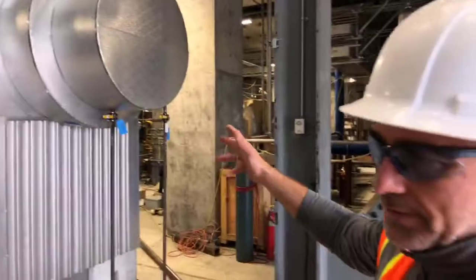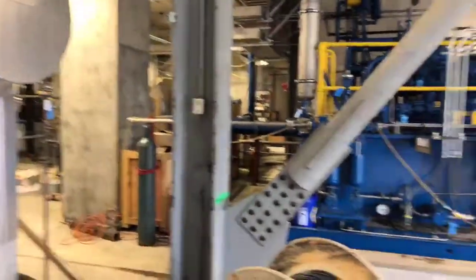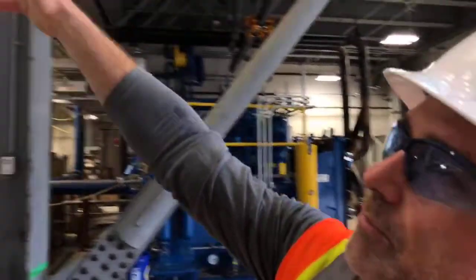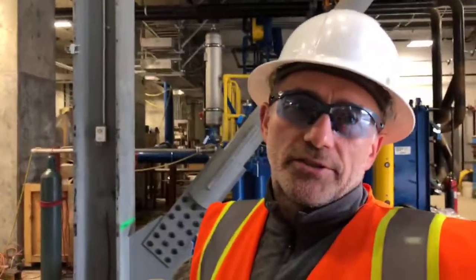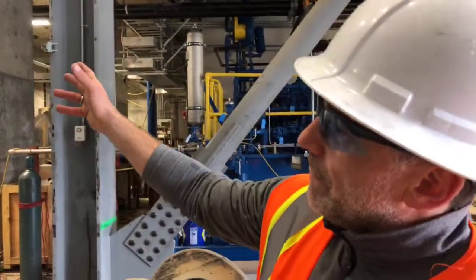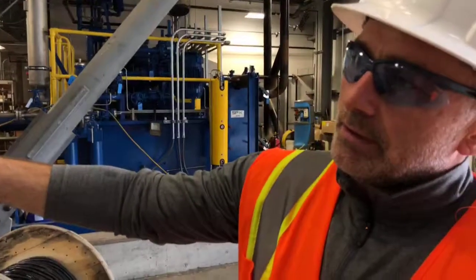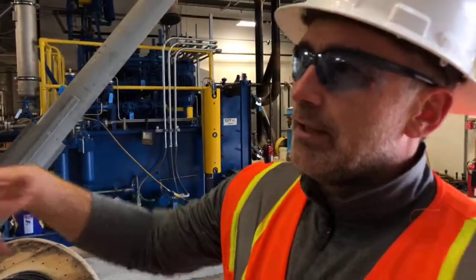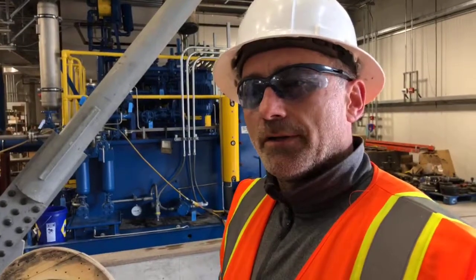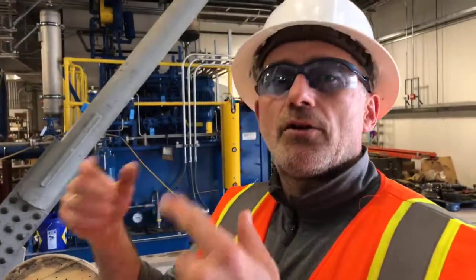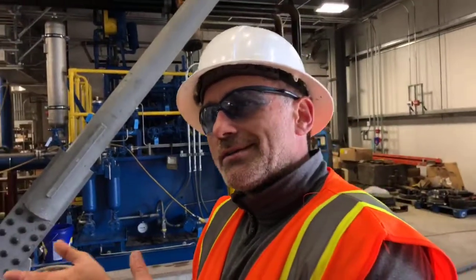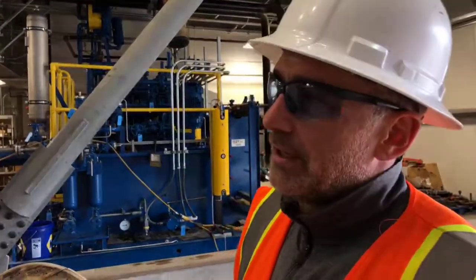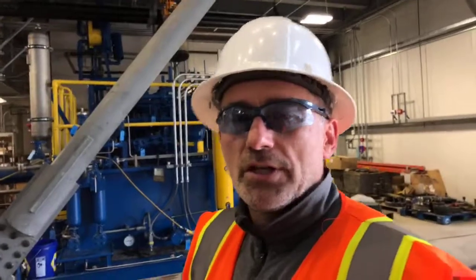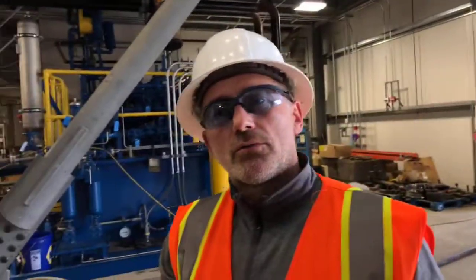This piece is basically a heat exchanger. In the winter, we take some of that exhaust steam we'd otherwise waste in the ACC unit, run water and glycol through it, and heat up that glycol. That glycol is sent to campus to the preheating coils in the buildings. It's low energy steam, and the glycol runs around 110 to 120 degrees, but it gives us free heating for the preheating coils. It's part of the same loop that in summer runs chilled water to the buildings to cool them, so in summer we don't use this part.